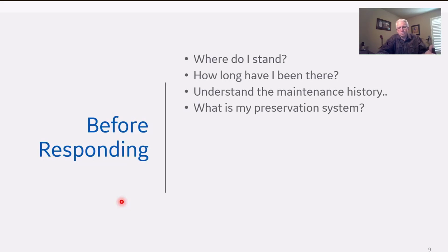But if I've got an N2 system and I'm replacing the bottle, let's go back to that again. If I've got a nitrogen blanketed transformer and I'm replacing that nitrogen bottle once a week, once a month, or maybe once every 2 or 3 months, you shouldn't be replacing that nitrogen bottle very often at all. I'm sweeping that transformer and degassing it on a frequent basis. If that's happening and I'm building a lot of hydrogen in that transformer, it's time to worry about it, because at the moment what I'm doing is taking a broom and sweeping it out. So that would be a little concerning to me.